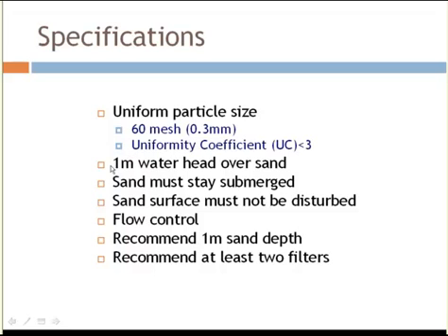A one-meter water depth over the sand is necessary to create the pressure to flow the water through the sand. Since it's a biological system, the sand must be submerged at all times, and the sand surface should not be disturbed. Critical is flow control — if the flow rates are too rapid, we have found that depending on water quality, the pores in the sand bed can plug prematurely, which means maintenance is required to restore proper flow. Slower flow rates are beneficial in ensuring that proper treatment occurs.